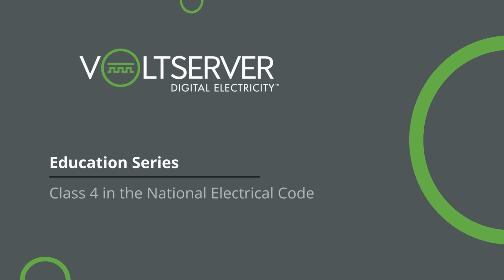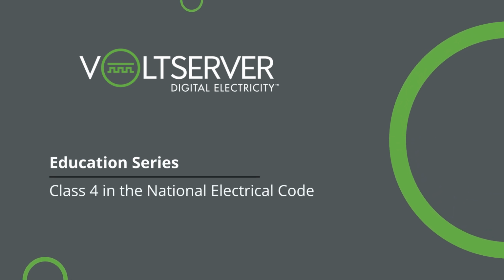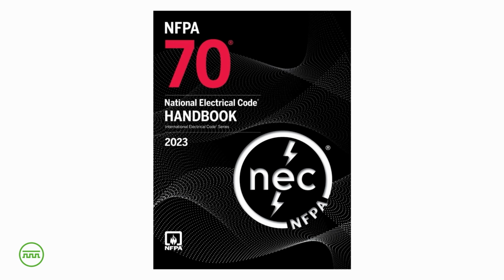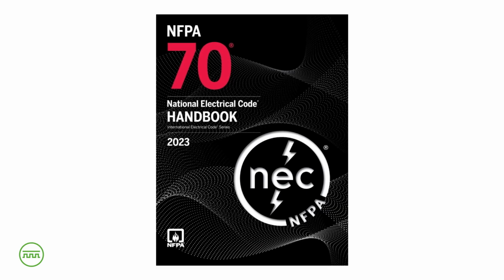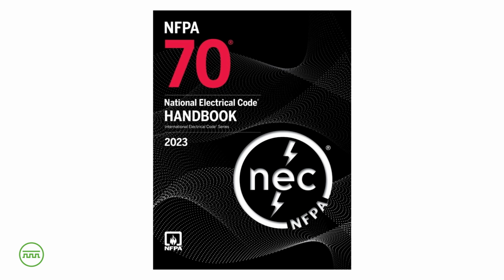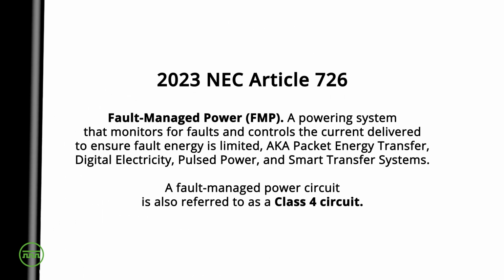This new type of power is moving quickly into the mainstream. With the 2023 edition of the National Electrical Code, released in fall 2022, fault-managed power is recognized for the first time. Class 4 systems are unique and specialized enough that they have their own code section within the National Electrical Code. Class 4 circuit requirements can now be found in Article 726, Class 4 Fault-Managed Power Systems.